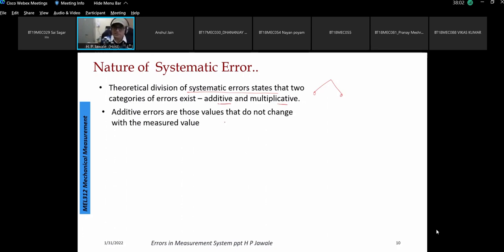Additive errors are those values that do not change with the measured value. For example, consider a micrometer. When the probe is touched to zero, the reading shown is plus 0.002 millimeter. If I insert an element of 5 millimeter diameter, the readout will show 5.002. For 10 millimeter diameter, it will show 10.002. For a 15 millimeter bar, it will show 15.002.